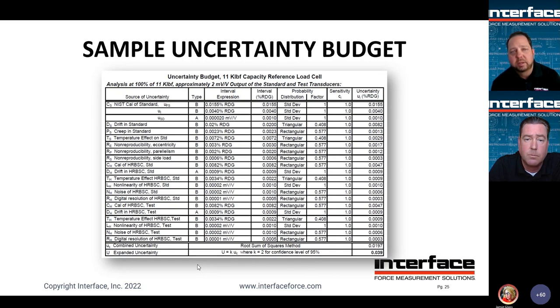In the right column there, you've got the NIST cal, you've got potential drift and creep in the standard. Then you've got the temperature effect, which is going to be a function of the lab, of course, in terms of the actual contribution there. Reproducibility aspects, noise level aspects, and then you see down here the HRBSC, that's the instrumentation side. So you've got the load cell or a torque sensor, perhaps, calibration reference standard, contributions from that. Then you'd have the contributions from the instrumentation to arrive at a total system level. So this is an example that we've assisted some customers with to come up with some direction. I would just say that a lot of it comes down to an individual lab's confidence in their processes and how well they can control each of these different elements. All right, next slide.